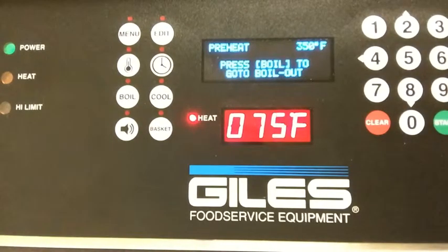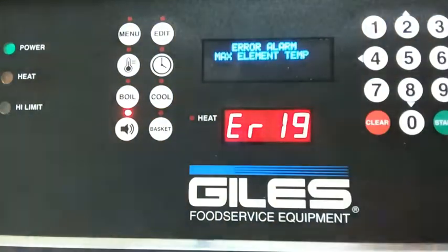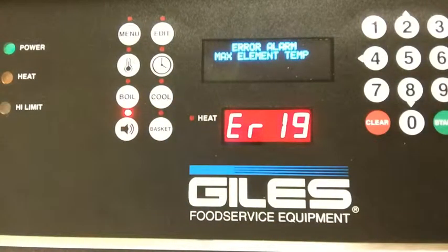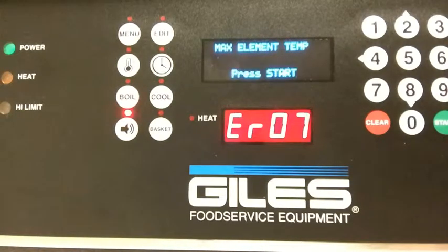Now if we were to have the unit running and the oil got below the element, that element sensor would definitely cause it to go into alarm. And when it does, it will display on here, like there, error alarm, max element temperature. It's exceeded the max element temperature setting that we established back during our user settings. So we're going to get an ER19. Now, if for whatever reason it cools back down, it will allow it to reset by pressing start.